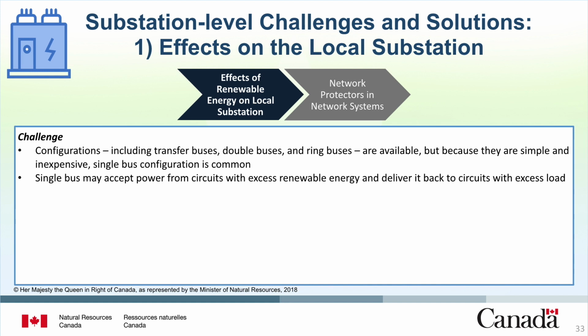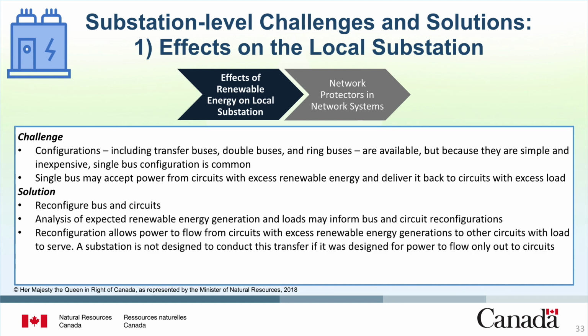A substation is not designed to conduct this transfer if it was designed for power to flow only out to the circuits. The solution to this challenge is to reconfigure bus and circuits. In configurations other than a single bus, sectionalizing switches or isolation switches must be positioned for this exchange of power to occur, and new legs between circuits may need to be added. Analysis of expected renewable energy generation and loads may inform required reconfigurations to the buses and circuits.